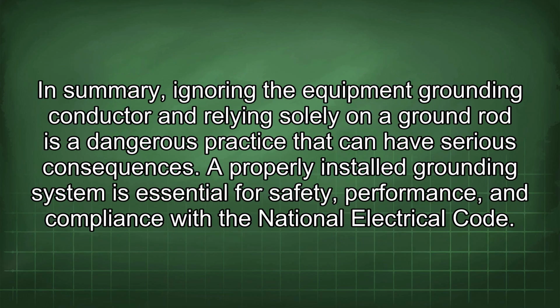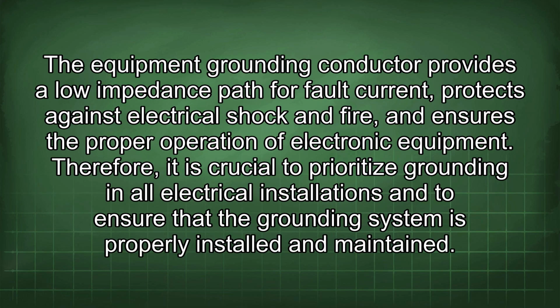In summary, ignoring the equipment grounding conductor and relying solely on a ground rod is a dangerous practice that can have serious consequences. A properly installed grounding system is essential for safety, performance, and compliance with the National Electrical Code. The equipment grounding conductor provides a low impedance path for fault current, protects against electrical shock and fire, and ensures the proper operation of electronic equipment. Therefore, it is crucial to prioritize grounding in all electrical installations and to ensure that the grounding system is properly installed and maintained.